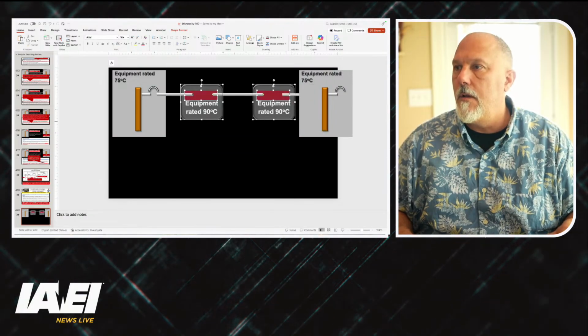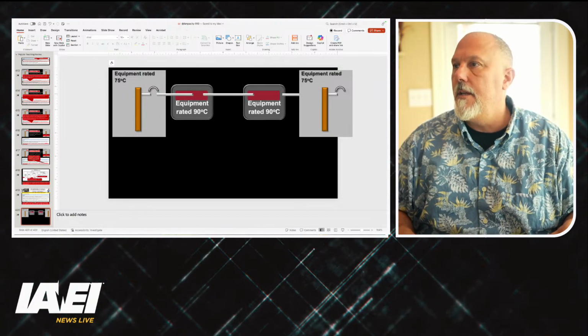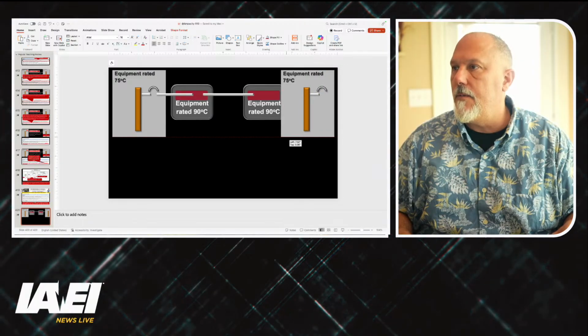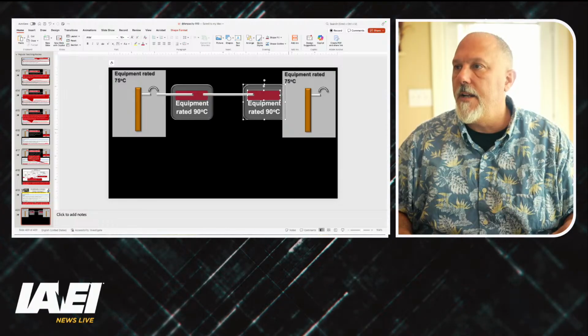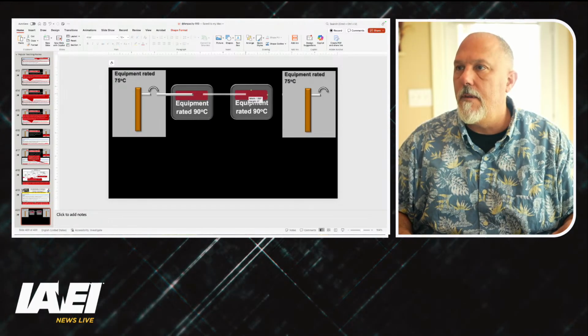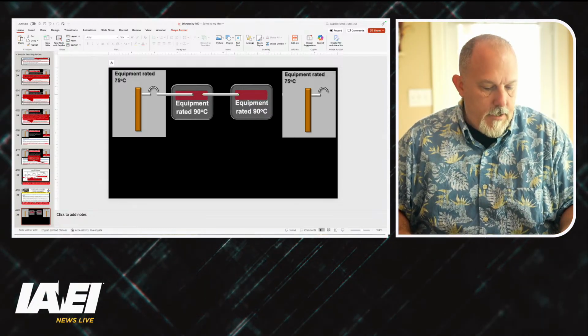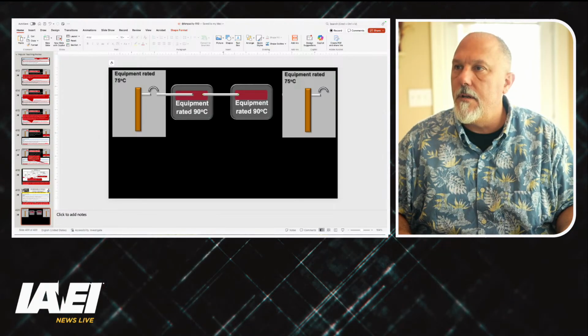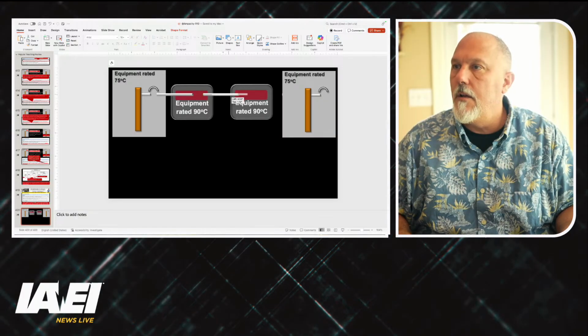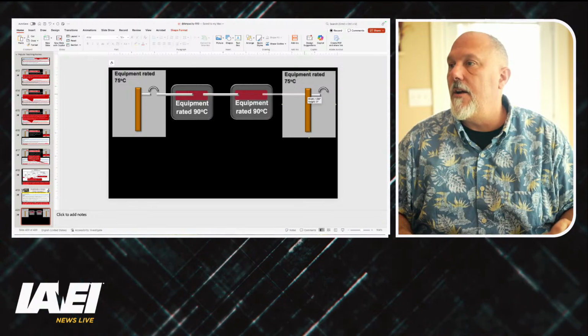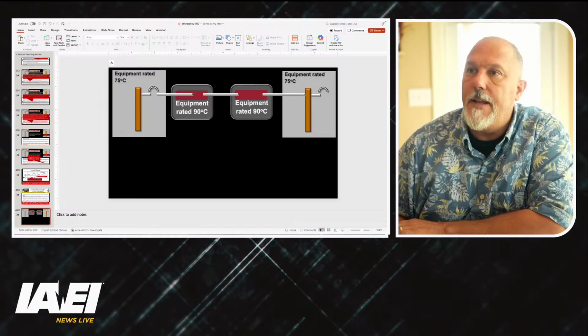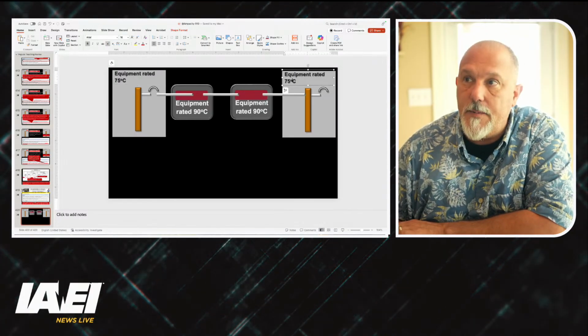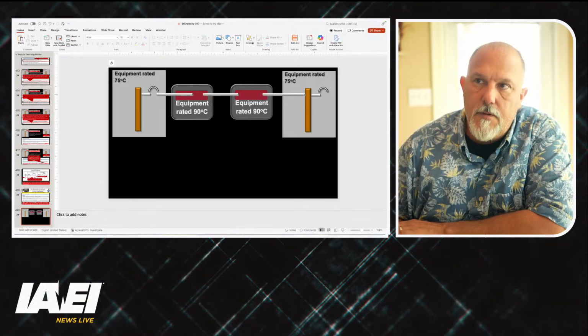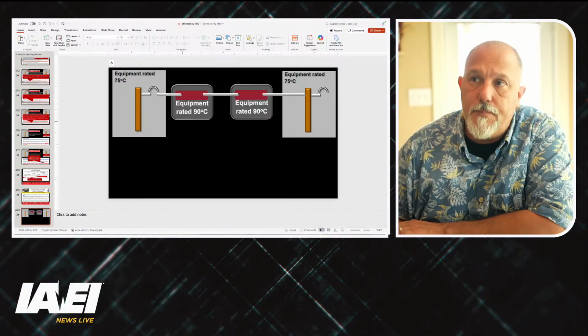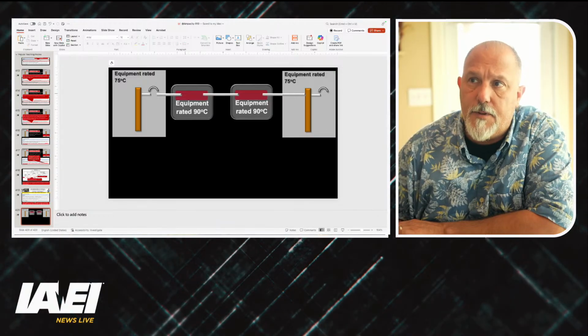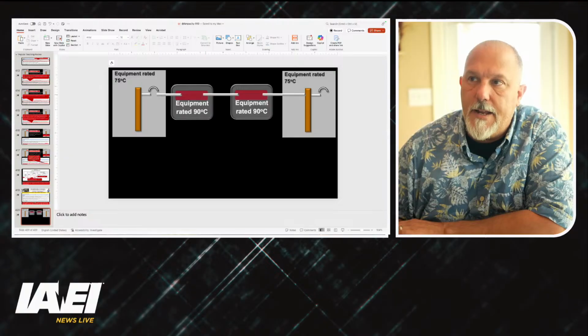I'm going to move this over this way, and I'm bringing this over this way. There we go. All right, so let's say, for example, that I have 75 degrees C equipment here, 75 degrees C equipment here. I come off of this breaker and I land on, say, a terminal block, a piece of equipment that's rated 90 degrees C with a terminal block in there, and then I come from that 90 degrees C to this 90 degrees C.